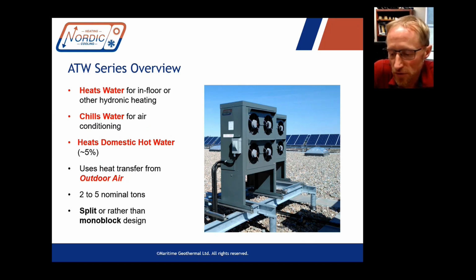So that would be useful in case you have space for all these tanks, of course. And also if you want to do dedicated domestic water preheating all summer, because if you chill your main buffer tank, you don't have any hot water heated in order to do domestic water preheating. Well, so I guess the question is, are you using the waste heat from the cooling, or are you just switching out of cooling mode and now you're in heating mode, but you're doing hot water?